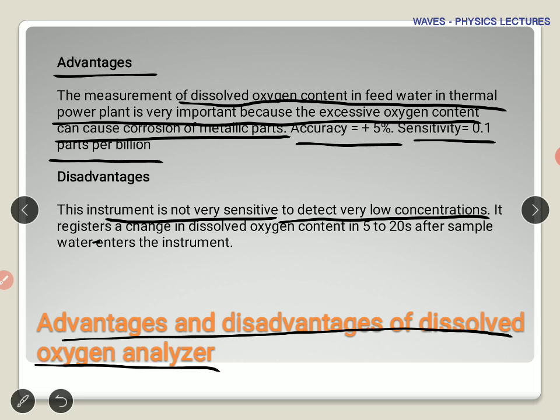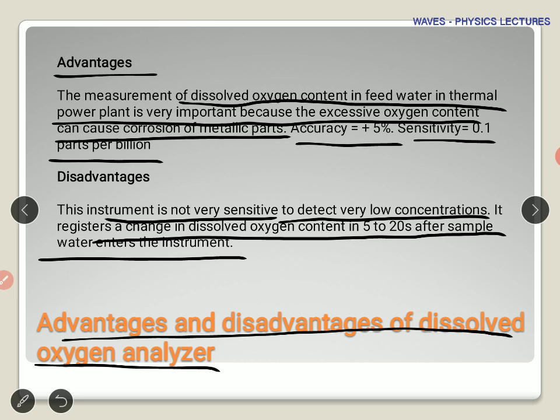Another disadvantage of oxygen analyzers is that they register a change in dissolved oxygen content only 5 to 20 seconds after the sample water enters the instrument. So if dissolved oxygen is present at a minimum level, it cannot be detected at the initial stage — meaning the instrument response is delayed and it's not sensitive enough to catch low dissolved oxygen early.